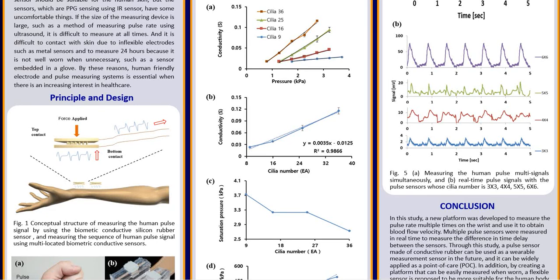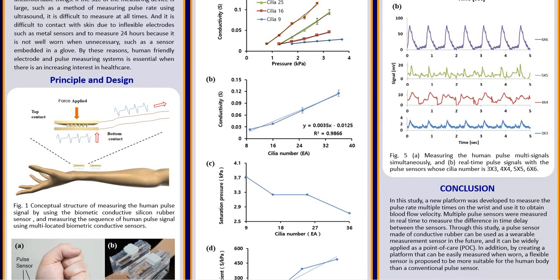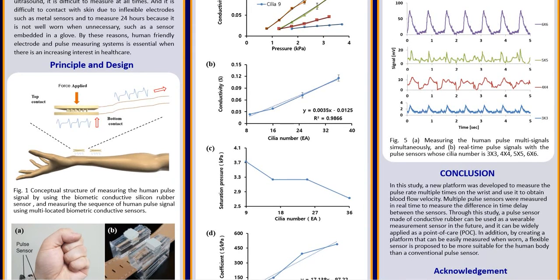The stronger the pressing pressure, the higher the electrical conductivity, and the greater number of cilia, the greater the rate of change. However, when the number of cilia is high, it tends to be saturated more quickly. And using this, we are able to create a sensor optimized for blood flow velocity measurement.